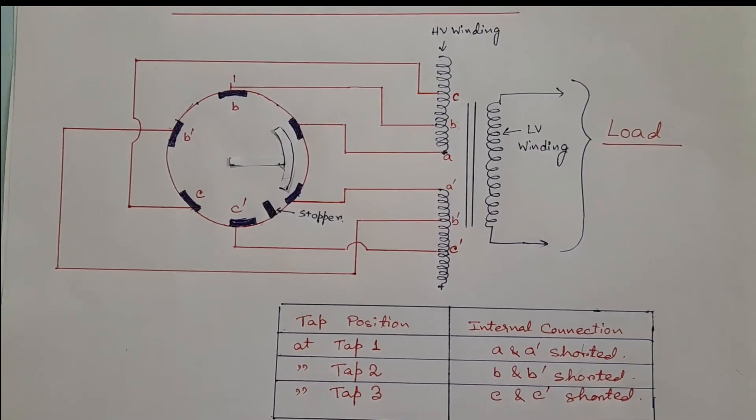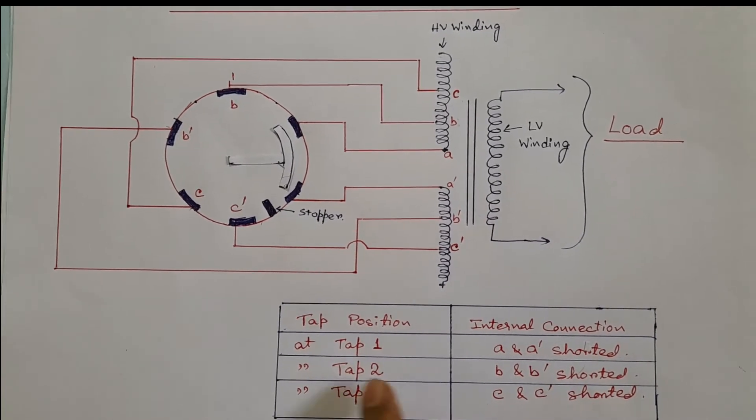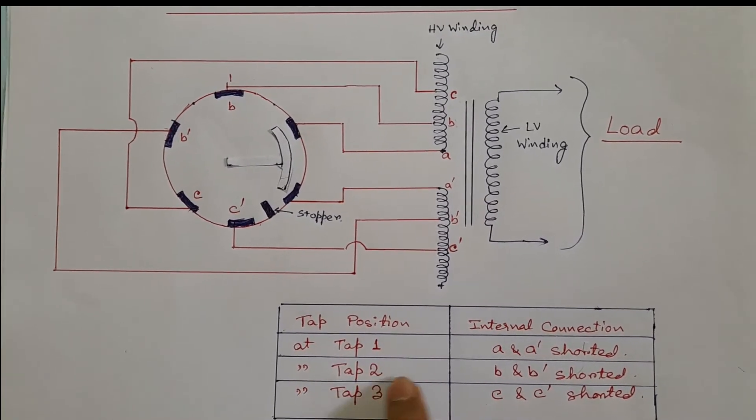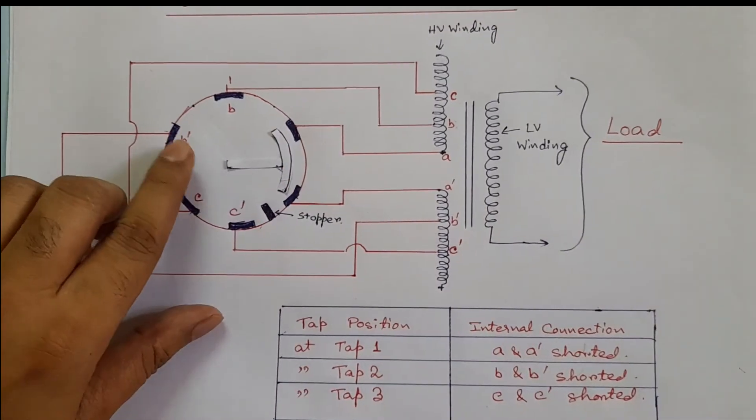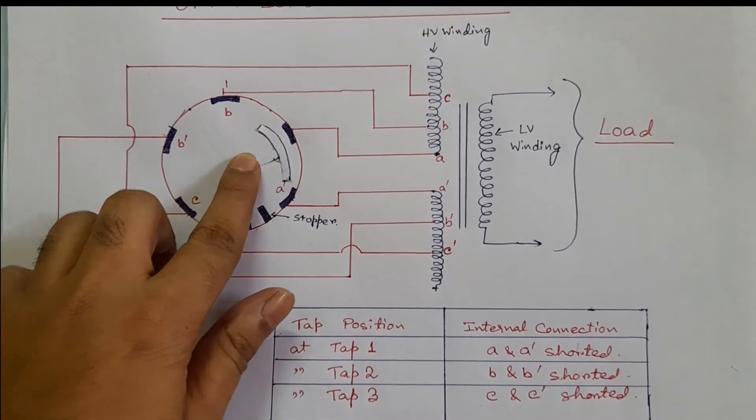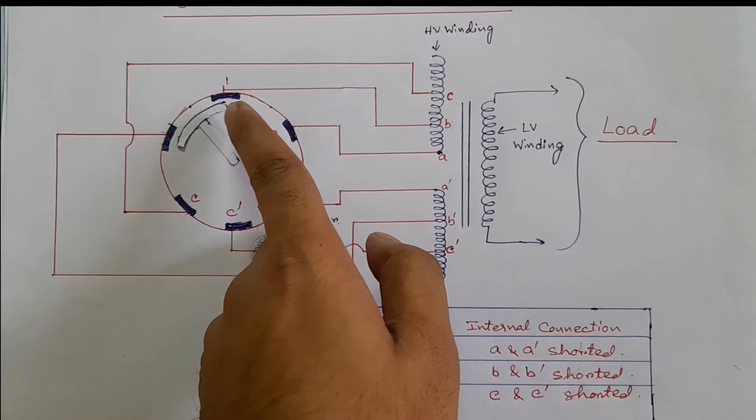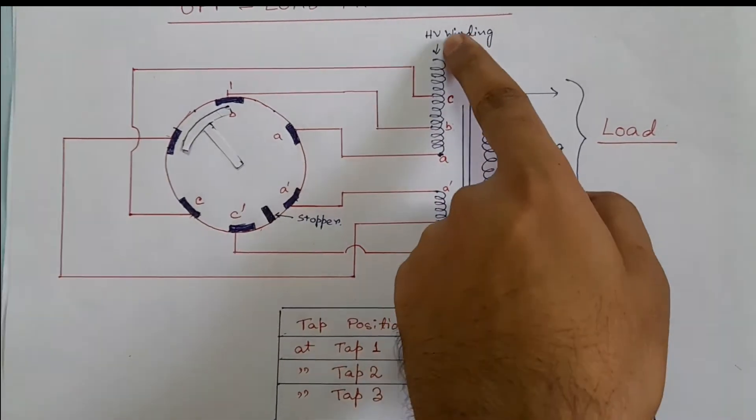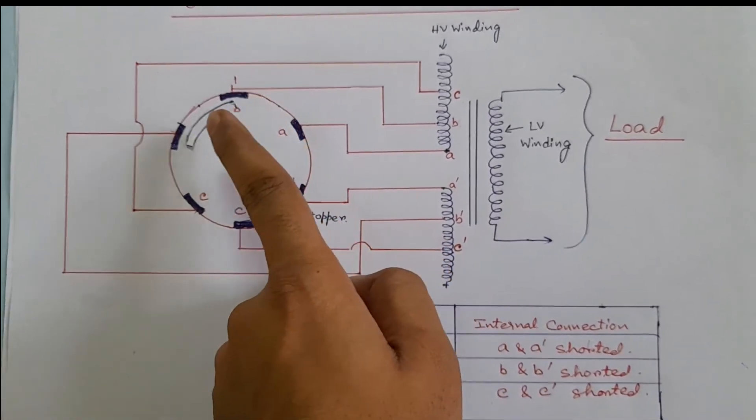Now we want to change tap position from one to two. In tap position two, B and B' must be shorted. So we will rotate this rotary switch, and at this position, B and B' terminals are connected. So HV current will flow in this path.